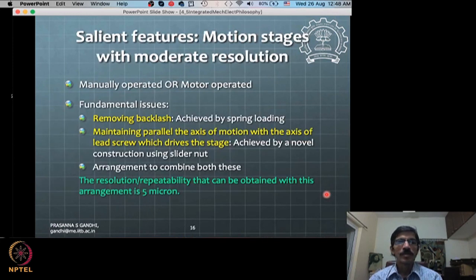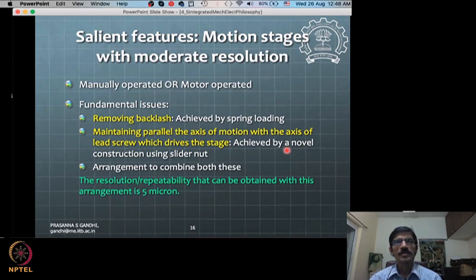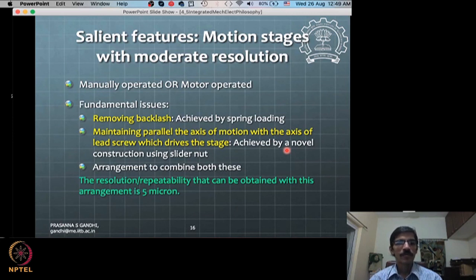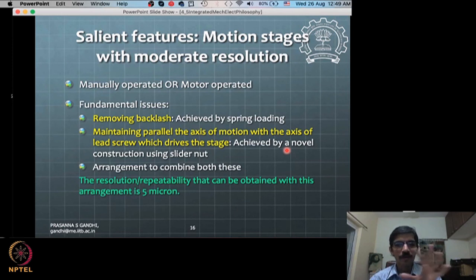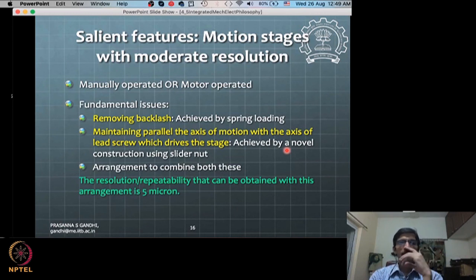To summarize: for removing backlash you create a preloading arrangement; for maintaining parallel axis motion and handling misalignment, a floating nut cage arrangement is used. These mechanical design choices reduce the burden on the control system, ensuring smooth motion without requiring complex control compensation.